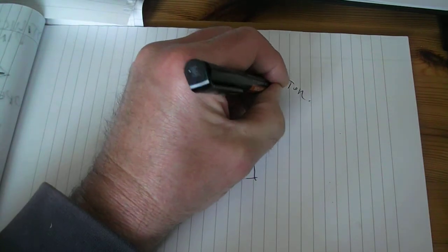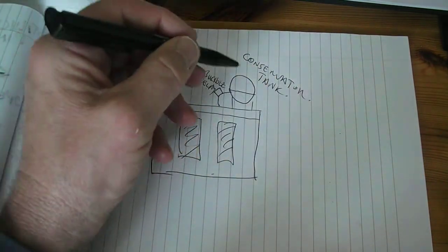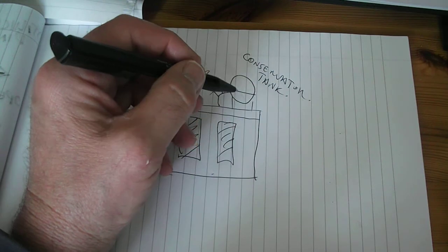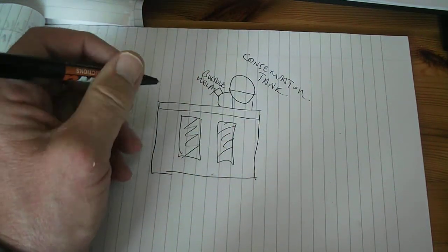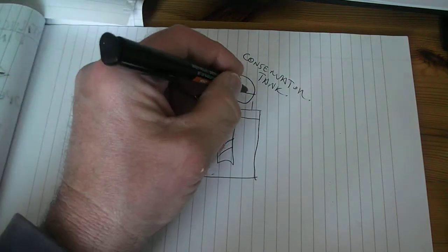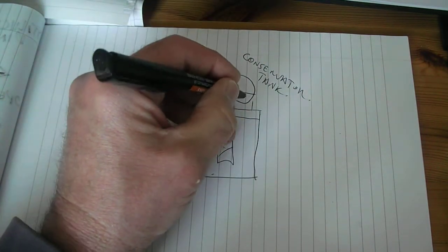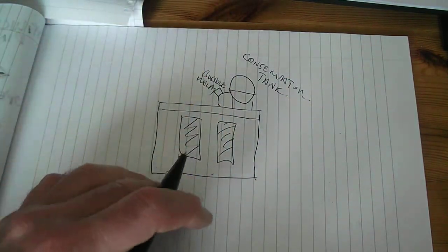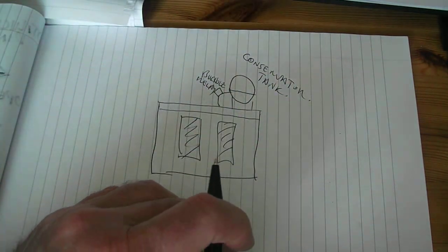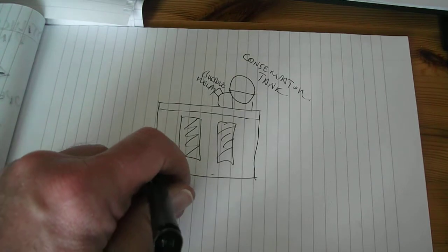But what you need to remember is the conservator tank, and its function is to allow for the expansion of the oil when it warms up due to transformer operation. When it cools down again, the gravity feed allows the oil to go back into the transformer.